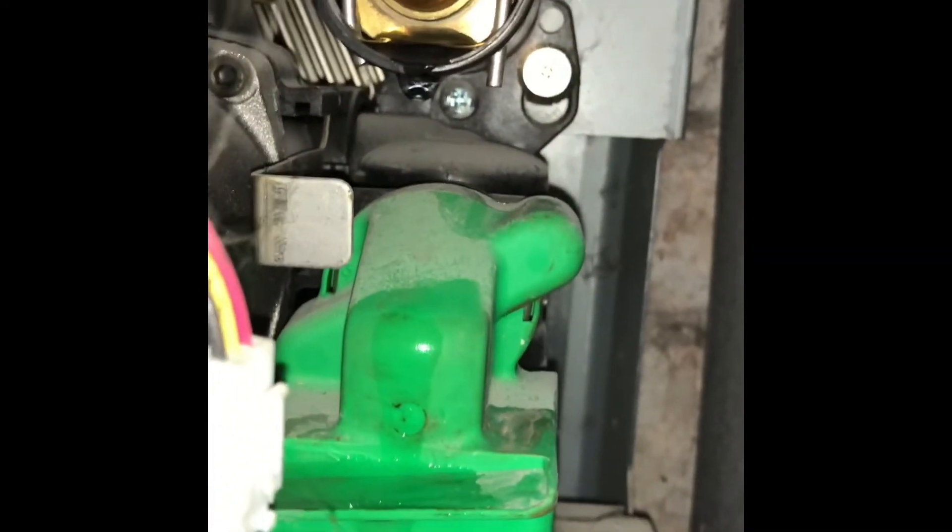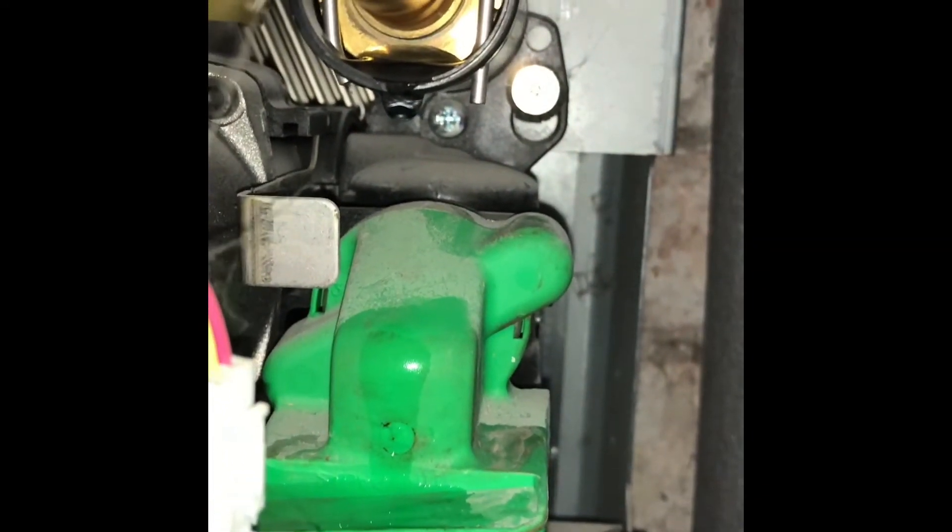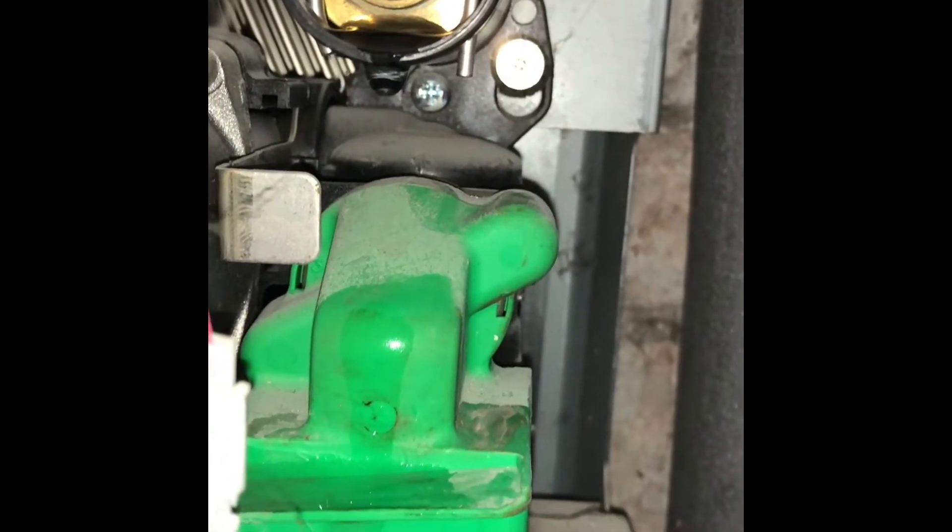What you're going to have to do is replace the right-hand side of the boiler — it's the plastic item that goes onto the pump and the diverter valve, and onto the secondary heat exchanger. Good luck with that one.